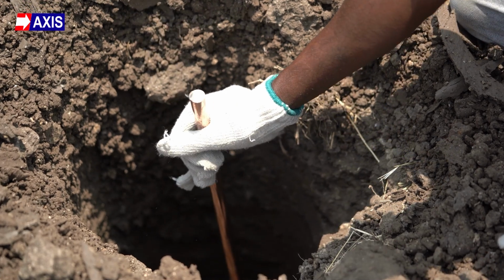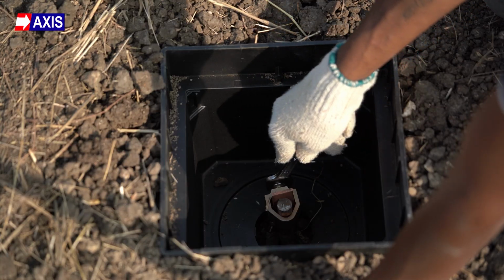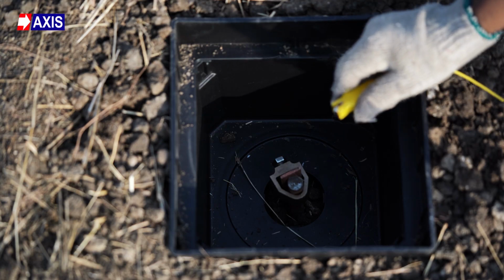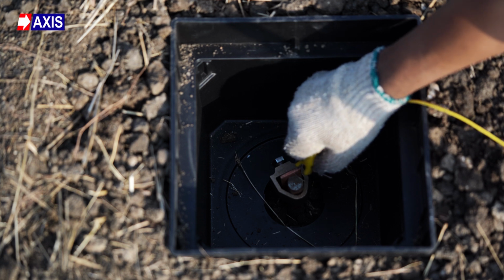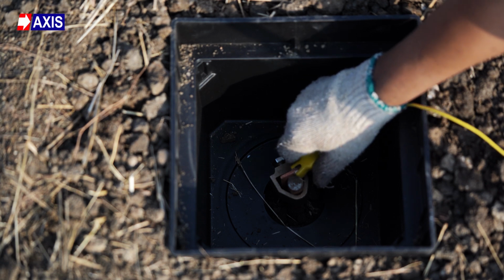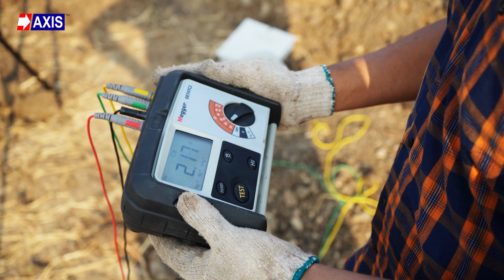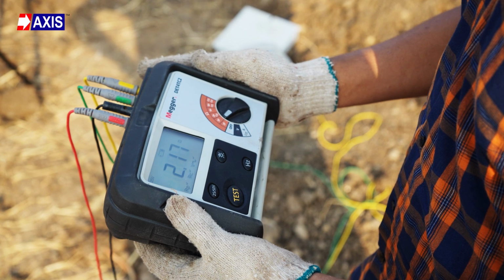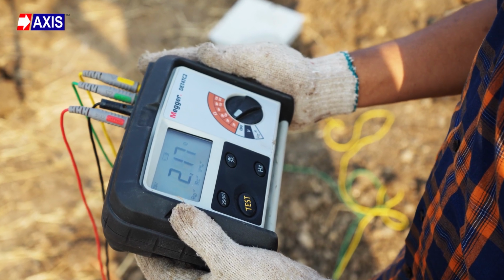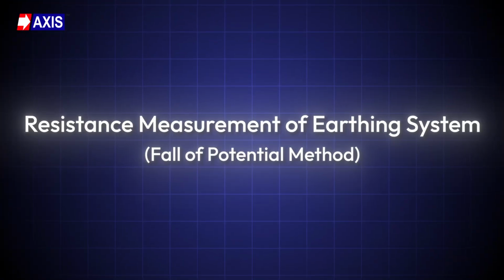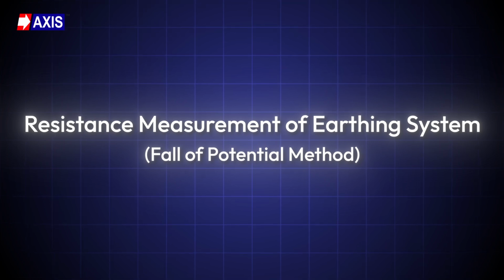You have just installed an earth electrode. The connection looks solid. The conductor is secure, but you still do not know if the electrode is actually doing its job. The only way to know is to measure its resistance. In this video, we will discuss the correct procedure for resistance measurement of earthing system.